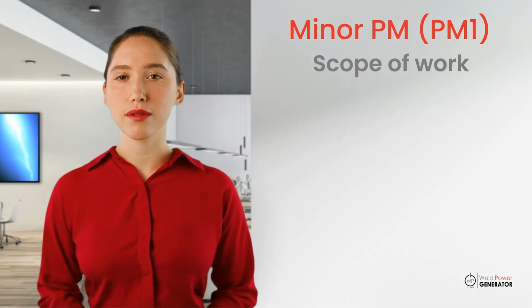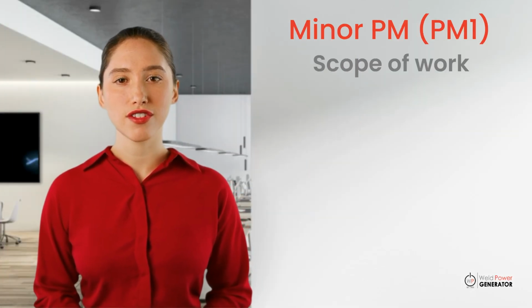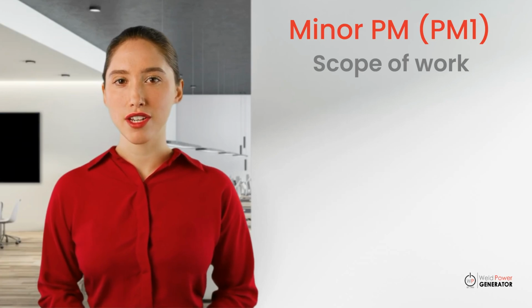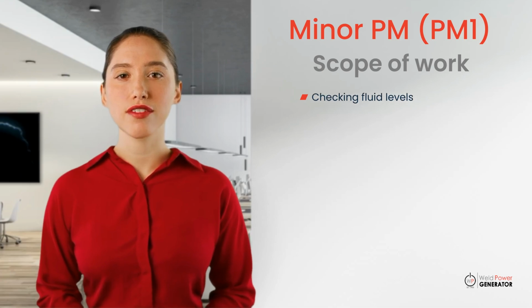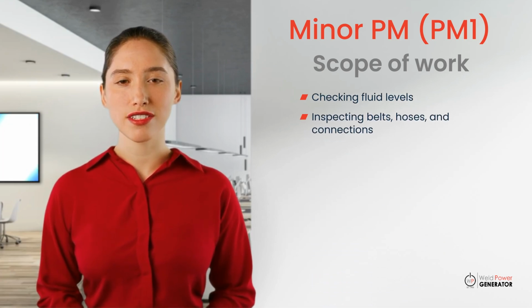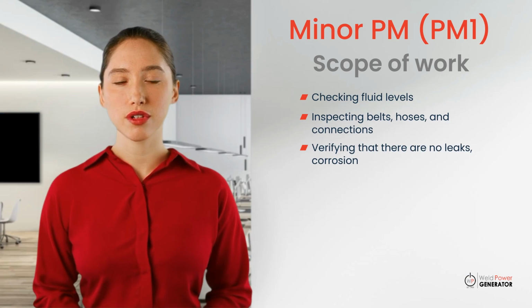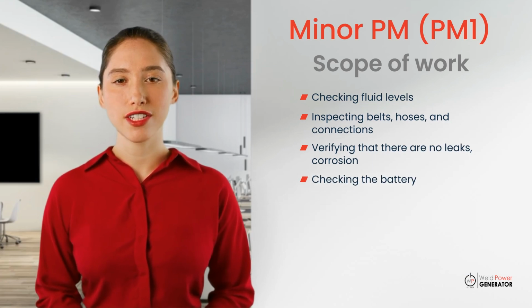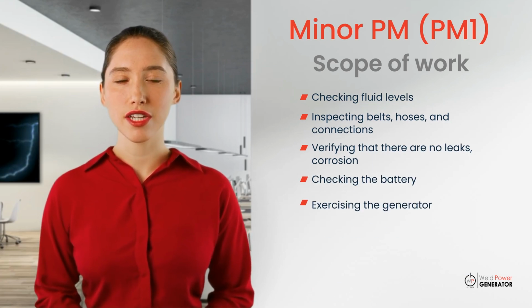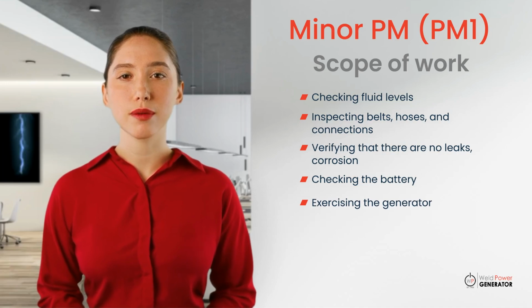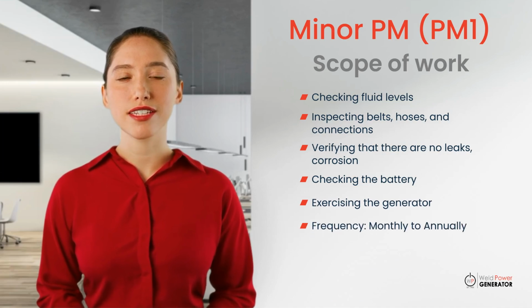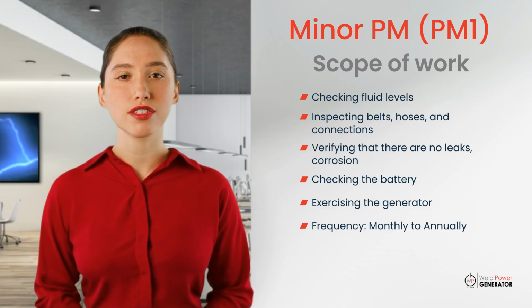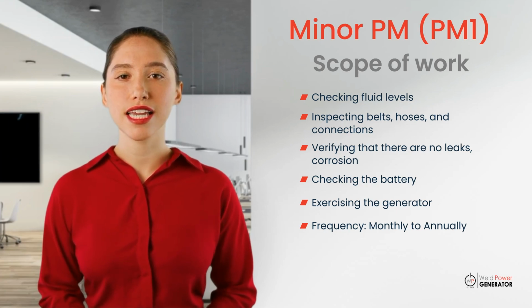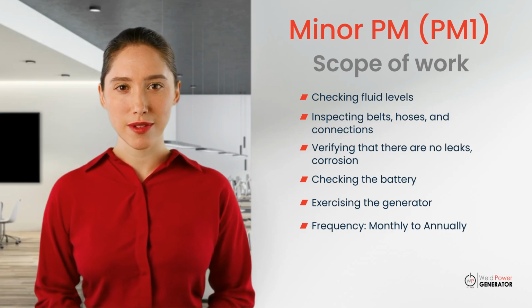A minor PM or PM1 involves a thorough check of the generator's essential components. During this service, we inspect fluid levels, belts, hoses, and connections, verify there are no leaks or corrosion, and ensure the battery is in good condition. Depending on the generator's usage and environment, minor PMs should be conducted anywhere from monthly to annually. Performing these checks helps identify and address small issues early, which prevents them from escalating into major costly repairs.